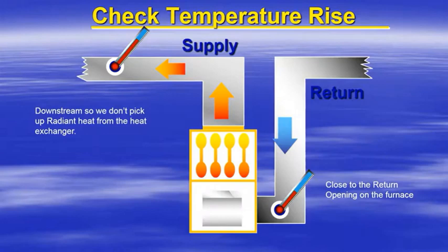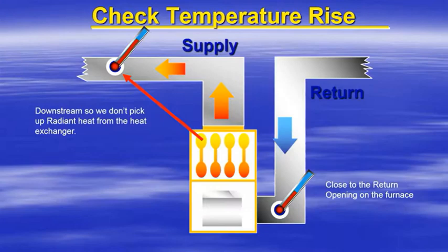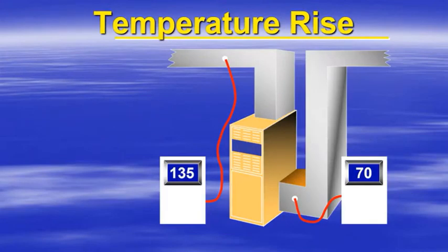To take the temperature rise on a gas furnace, you want to take the return air temperature close to the return opening on the furnace. We then want to take the supply air temperature downstream of the furnace so we don't pick up radiant heat from the heat exchanger.